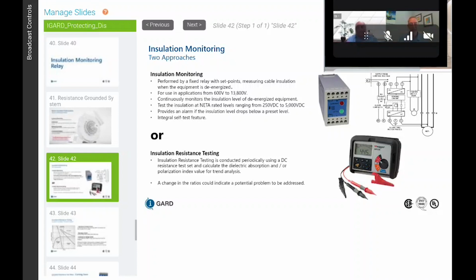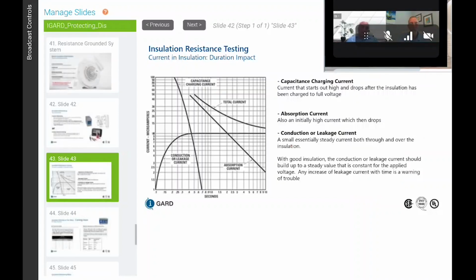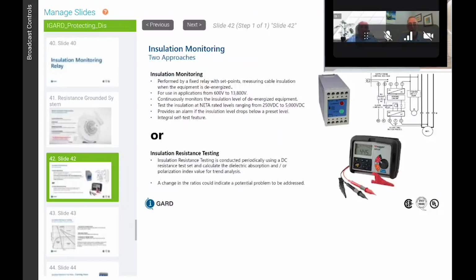And where we use a lot of these things is we already have one that's available now. The difference is the one that we have available now only puts 12 volts DC on the bus. The one that we're coming out with has 250, 500, 2,500, and 5,000 volts DC that you can put on the bus to measure the absorption and polarization index. But if you need one right now and you're good with 12 volts, it's available right now. Sounds good.